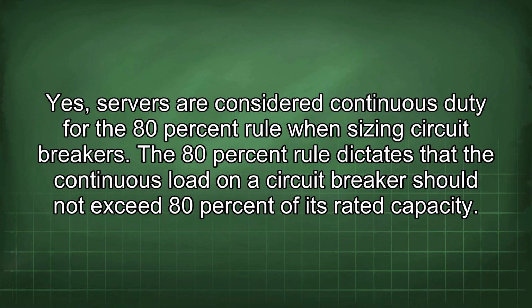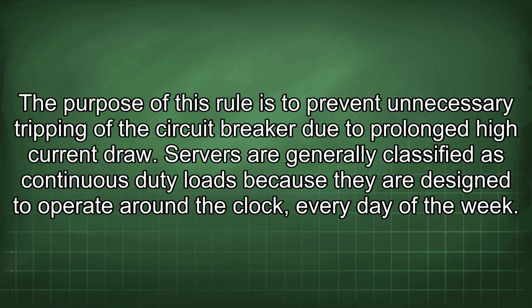Yes, servers are considered continuous duty for the 80% rule when sizing circuit breakers. The 80% rule dictates that the continuous load on a circuit breaker should not exceed 80% of its rated capacity. The purpose of this rule is to prevent unnecessary tripping of the circuit breaker due to prolonged high current draw.